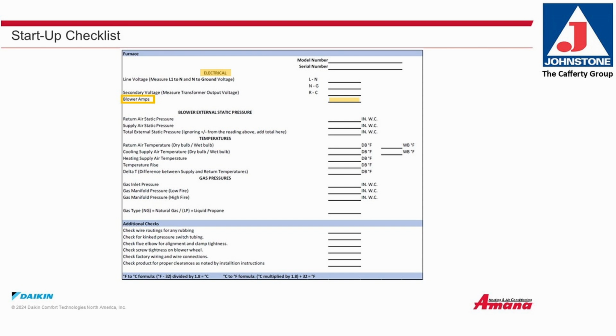Under blower external static pressure, here's a place for the return air static pressure, supply air static pressure, total external static pressure. Under temperatures, return air temperature, dry bulb and wet bulb, cooling supply air temperature, dry bulb and wet bulb, heating supply air temperature, temperature rise, and the delta T, or the difference between the supply and return temperatures. Gas pressures: inlet gas pressure, inches of water column, gas manifold pressure, low fire, gas manifold pressure, high fire, gas type, natural gas, LP.